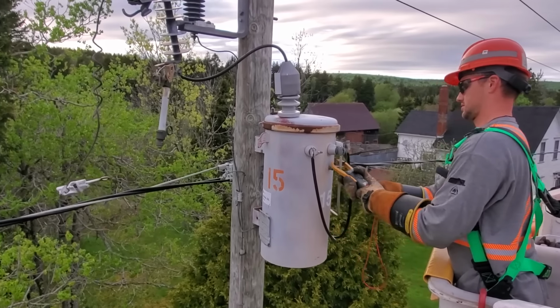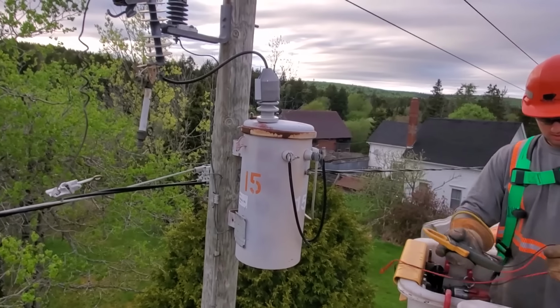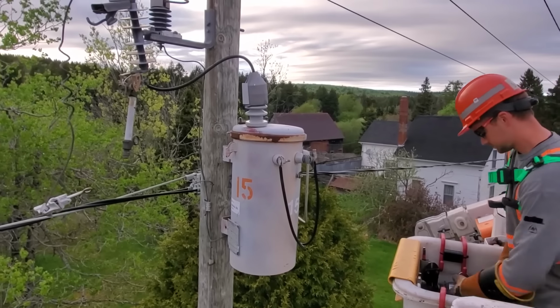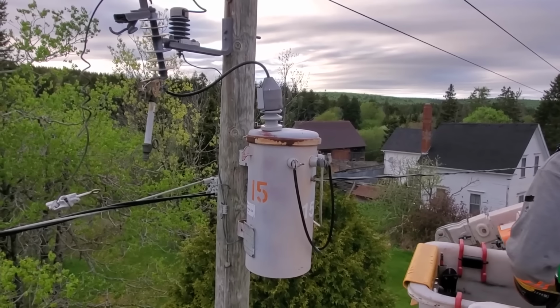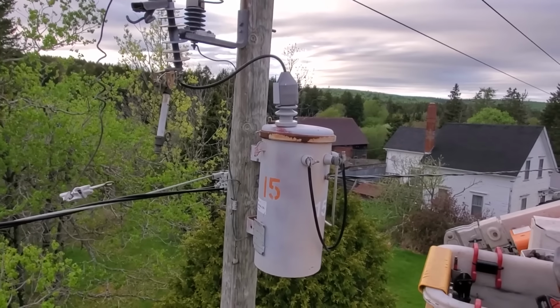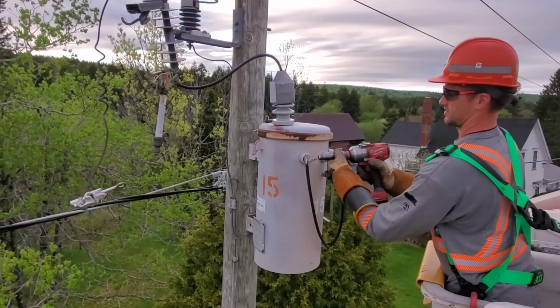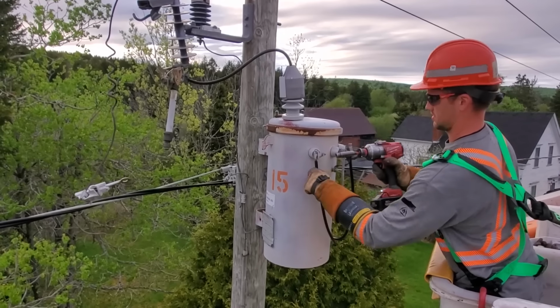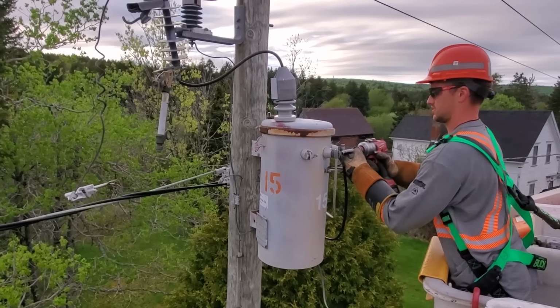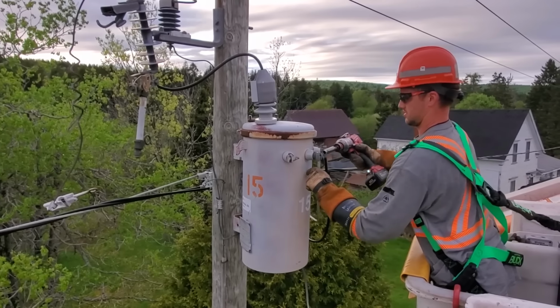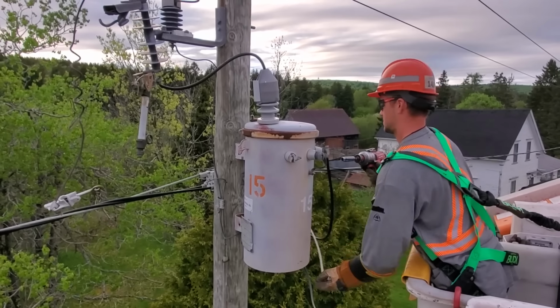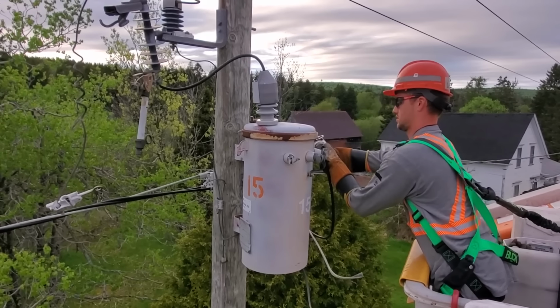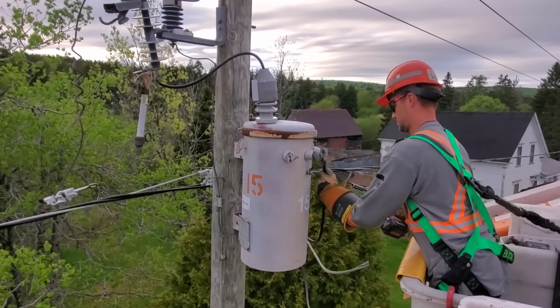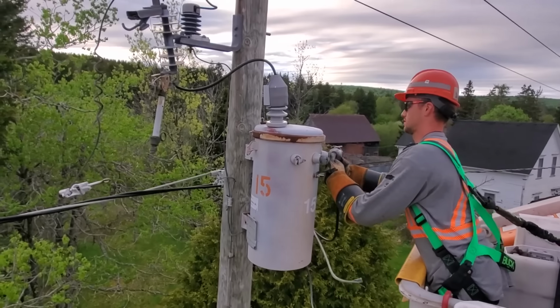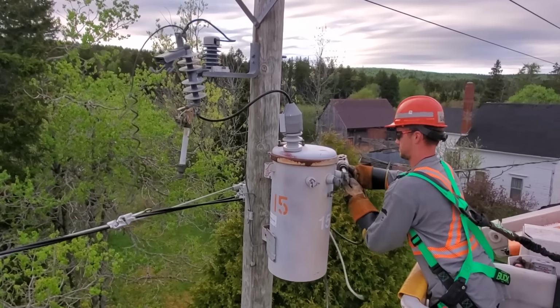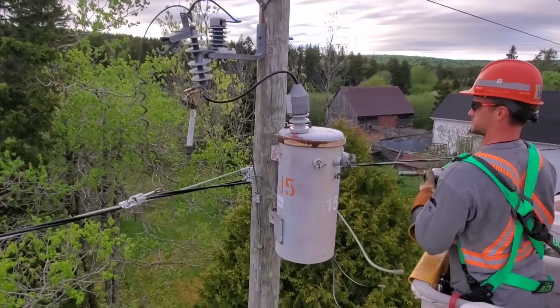So part of our procedure is always to install secondary grounds on the transformer whenever working on them. In a case where we're removing the transformer completely, there's not much point in installing secondary grounds, simply to take them back off. So as long as we remove the secondary from the transformer first, then we don't have to worry about any backfeed. So that is always the first step, and then the last step will be to install the secondary grounds once all the primary is installed.